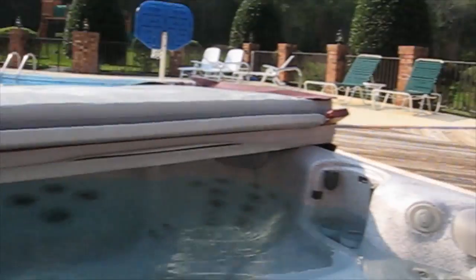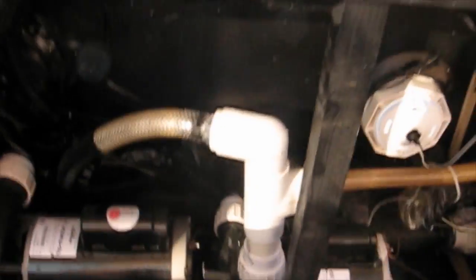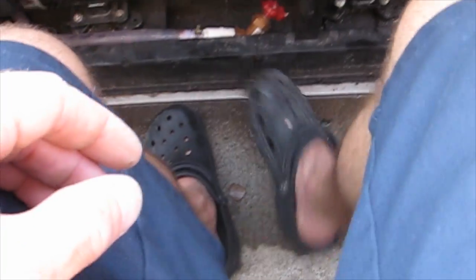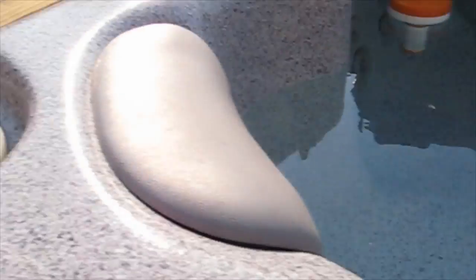Now this customer wasn't even complaining about this tub having electricity in the water. The reason is, see, they've got a deck around it. So they're never touching ground while they're in this tub. But I felt it when I was standing here. You see my feet down a little wet and I reached in and touched the water and I felt a shock.